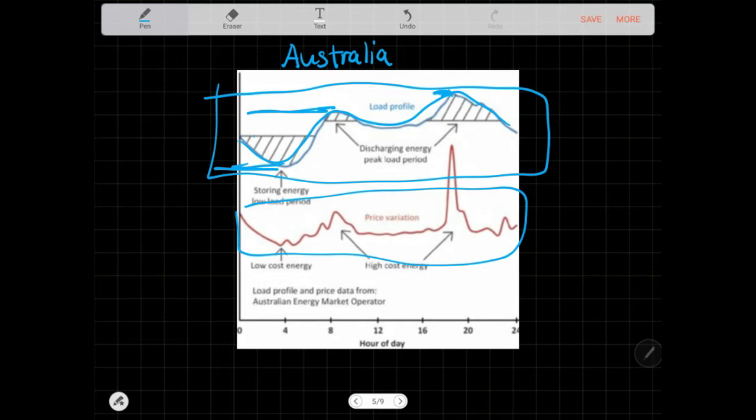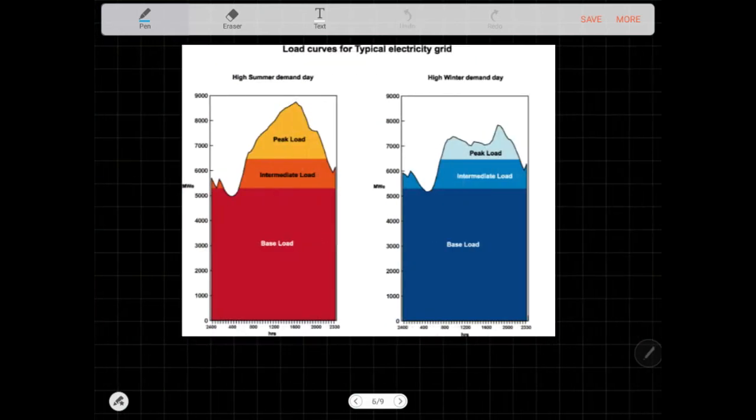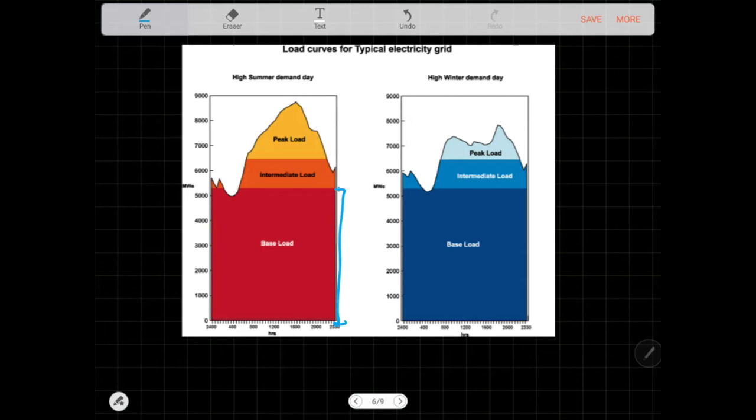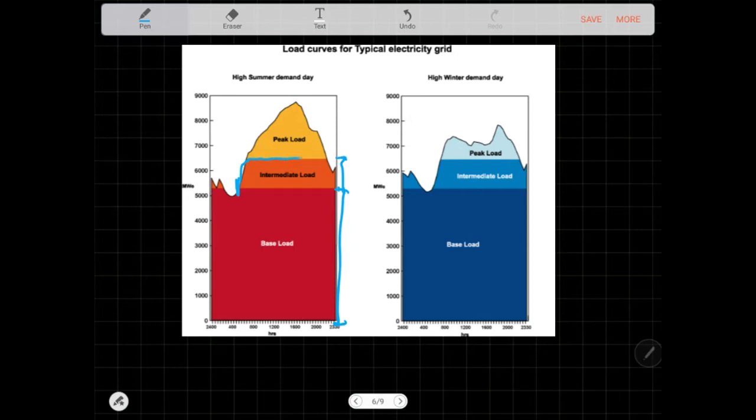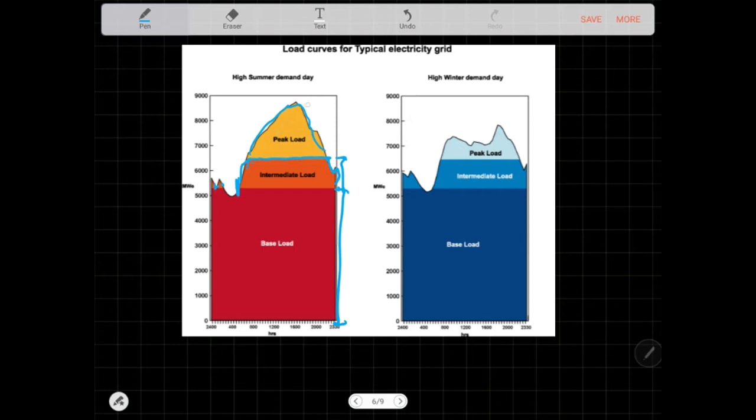So you need to figure out in this load demand what are the types of generators that we need. We have what we call baseload, which means they'll just keep running 24 hours no matter what happens because you always need them. Intermediate load is where you start up in the morning, they'll generate electricity for some time and then shut down at night. The peak load is where you cater for the rest. Each type of load needs to require different type of generators to fulfill its purpose.